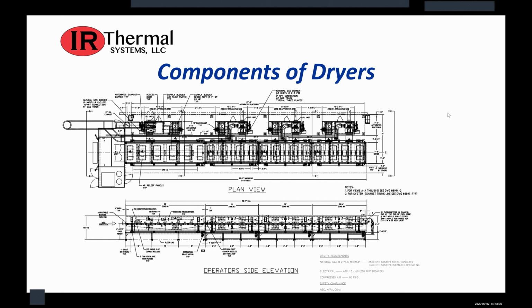The upper picture is the top view of the system. You can see the recirculation air plenums located adjacent to each zone, as well as, it's kind of hard to see because a lot of this stuff can get complicated, the makeup air and exhaust air are ducted in over top of each other in between those systems. It's also important to note that in a system like this, they had their recirculation air plenums located on an upper floor where it was a little more difficult to get access to.